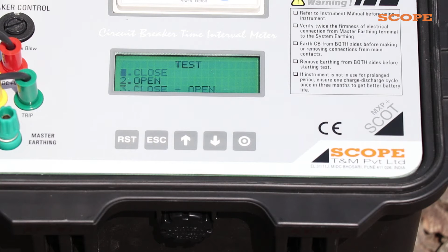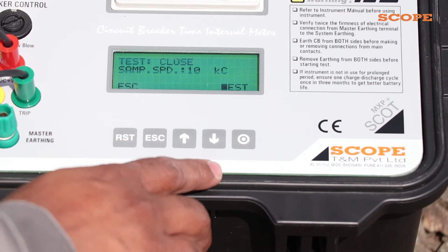First, we will check the closing timing of the circuit breaker. Select the close option and press enter. Now confirm the command by pressing enter. This will show the test timing.